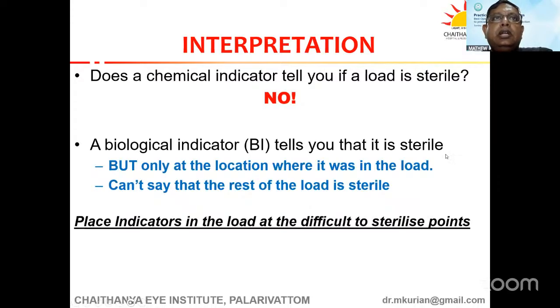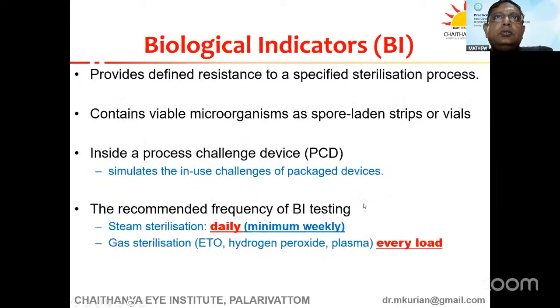Now, unfortunately, the chemical indicator does not tell if the load is completely sterile. It tells you that at the location where the chemical indicator was placed, it is okay. A biological indicator needs to be placed inside along with this at the place where the load is most difficult to sterilize. And this is also done in the process challenge device. So recommended frequency is daily for sterilization, but at least minimum weekly. That is what the NABH recommends. And for gas sterilization with every load.